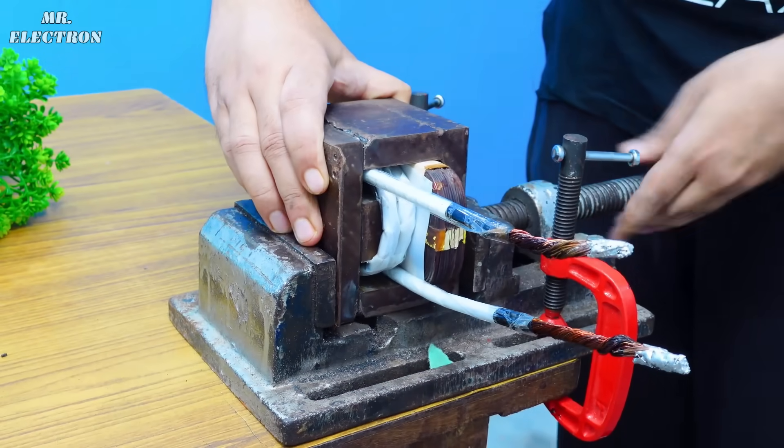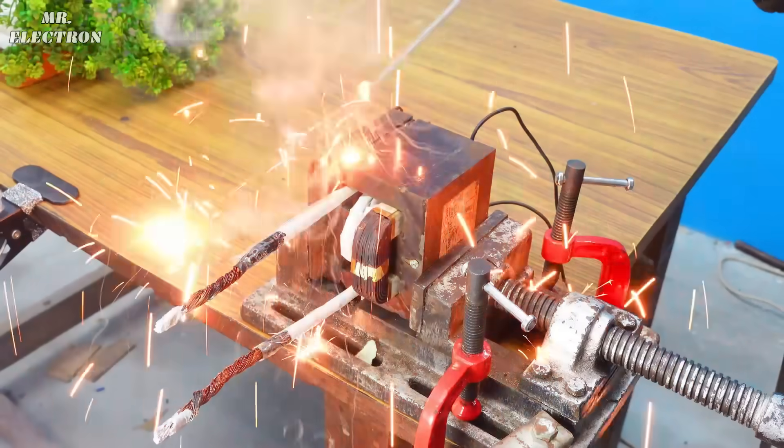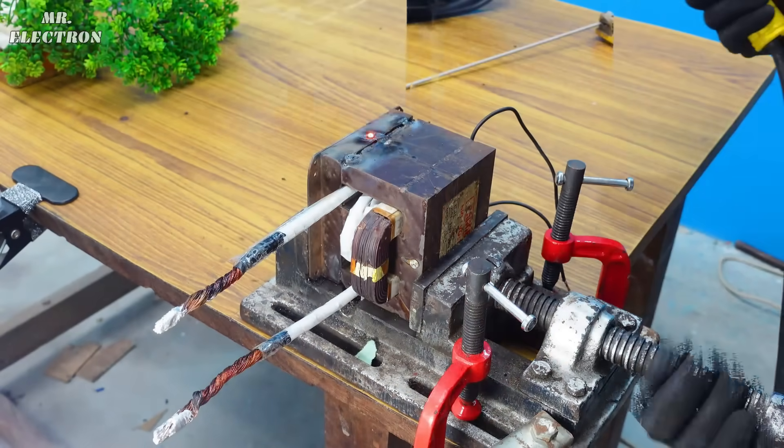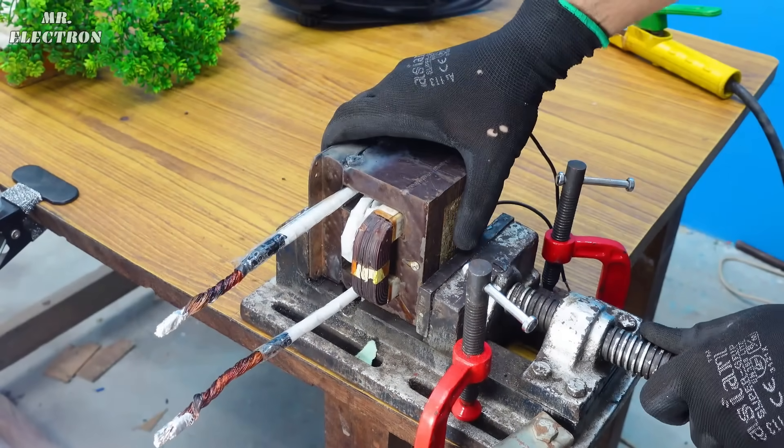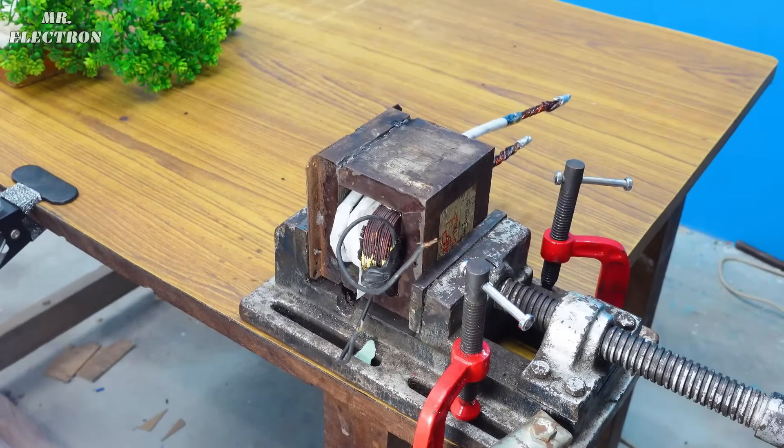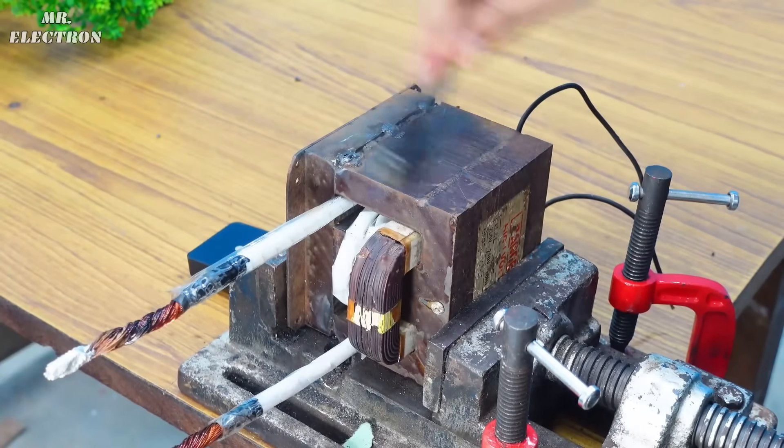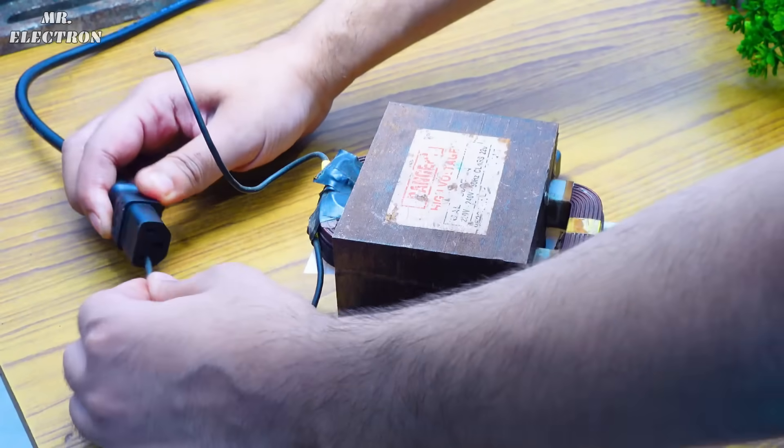All that is left is to do the welding of the core to complete the magnetic circuit. Here you can see I'm giving three arc welds on each side and there is an important reason behind that which I will be telling you later. Next comes the weld cleanup process and then starting with the test.